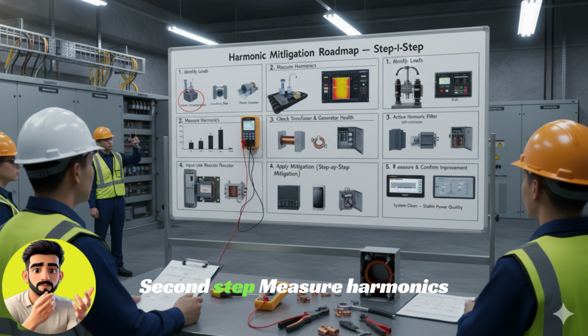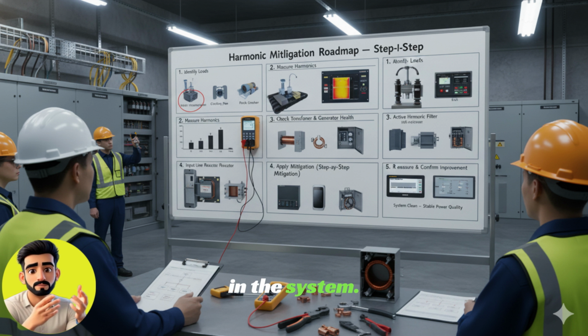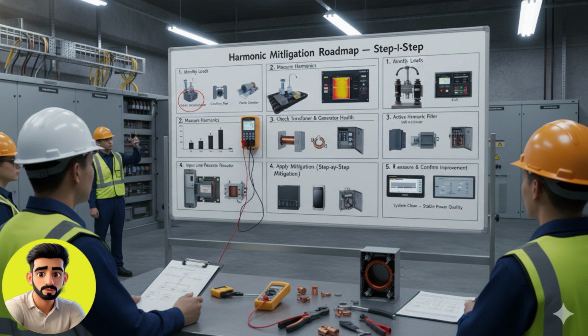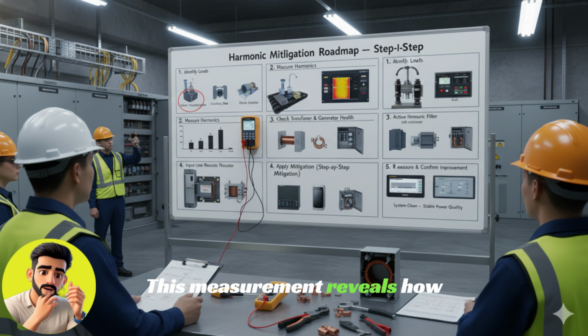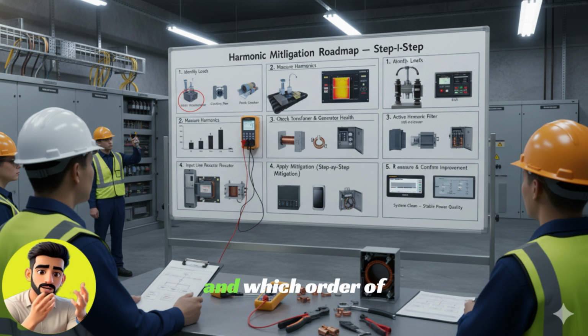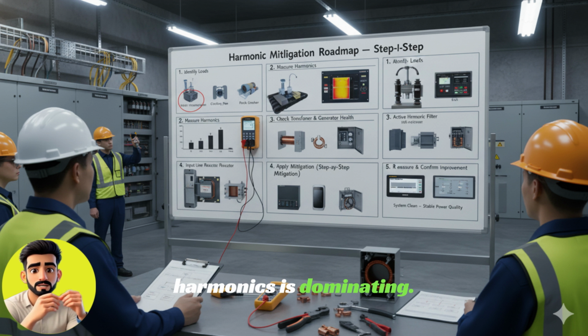Second step, measure harmonics in the system. Many plants make guesses. Harmonics will be high. Decisions are not made based on guesses. You need to measure current distortion and voltage distortion with an actual harmonic analyzer. This measurement reveals how high the harmonics are and which order of harmonics is dominating.